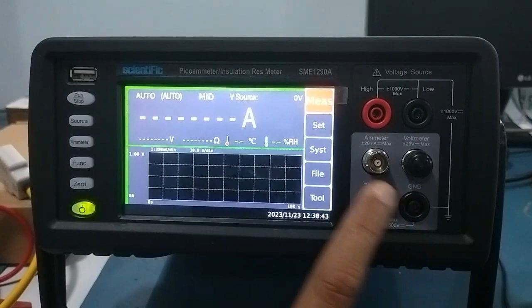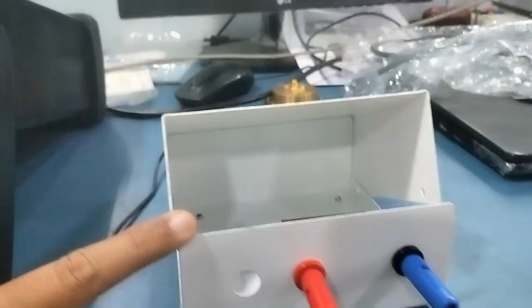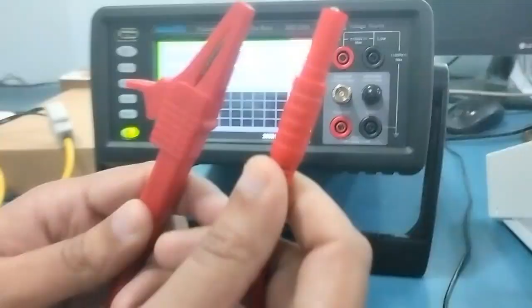To do the high resistance measurement, we need to connect our probe to high terminal to give voltage source to our device under test. Here we have connected one 10 giga ohm resistance, and we have to do the connection from device to the device under test. We will connect this high voltage cable to the high side of voltage source and connect it to the other side of device under test.